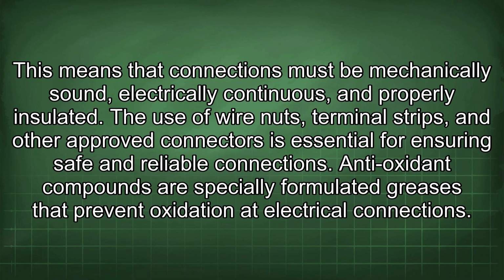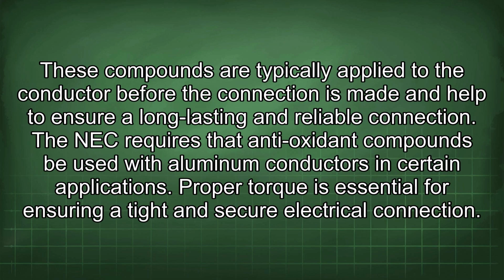This means that connections must be mechanically sound, electrically continuous, and properly insulated. The use of wire nuts, terminal strips, and other approved connectors is essential for ensuring safe and reliable connections. Antioxidant compounds are specially formulated greases that prevent oxidation at electrical connections. These compounds are typically applied to the conductor before the connection is made and help to ensure a long-lasting and reliable connection. The NEC requires that antioxidant compounds be used with aluminum conductors in certain applications.